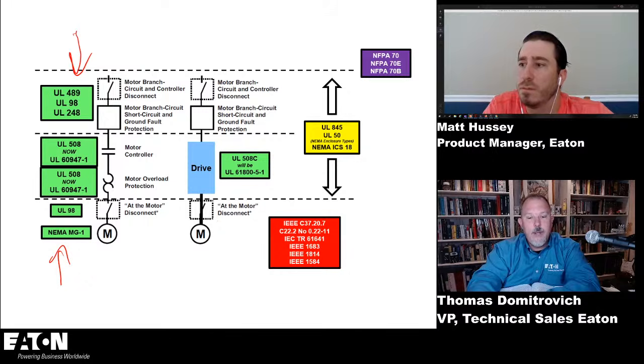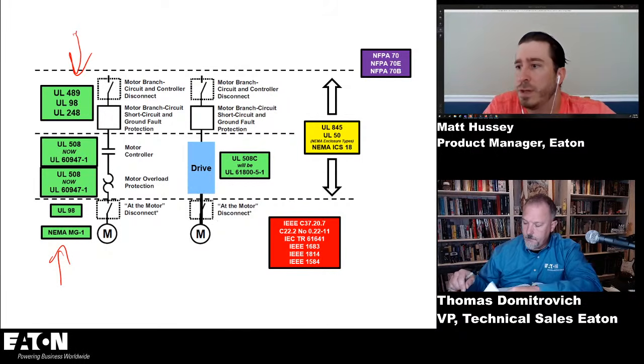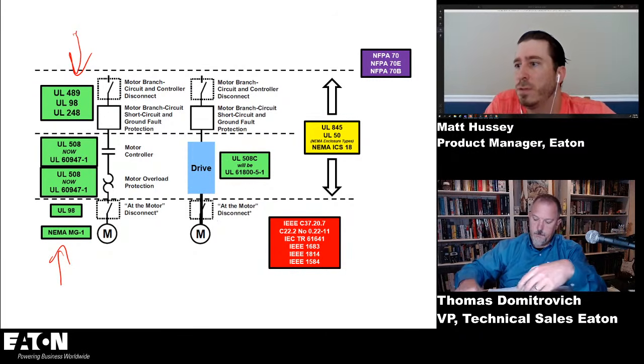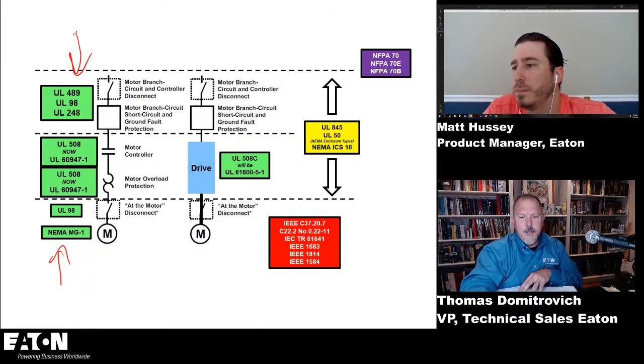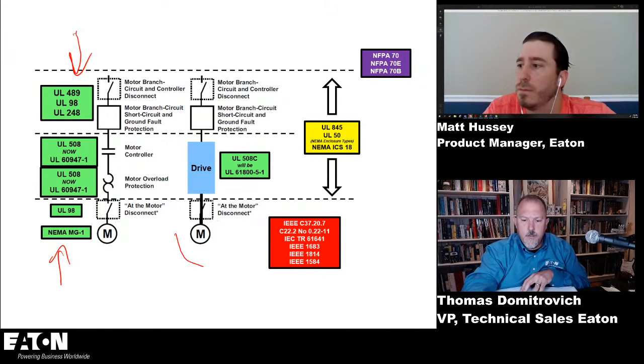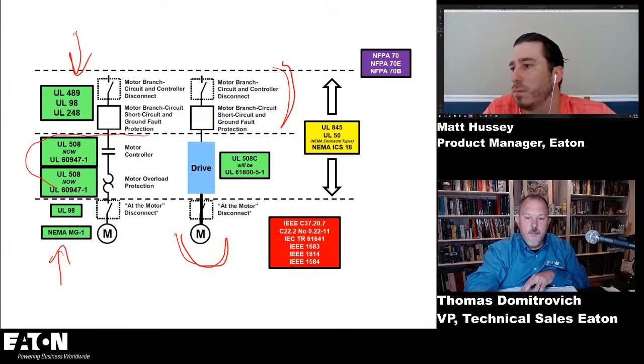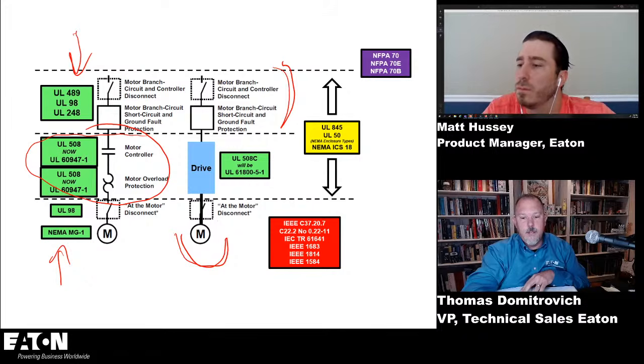And you say UL 508 now, UL 60947. Did a transition happen there? Yeah, there was a harmonization there with UL 508 as well as IEC 60947. Now it's a unified standard to work off of. And then we've got another UL 98 switch down there for the local motor disconnect. And what's this column over here? It includes the drive. That's the big difference there, right? Yep. So you have pretty much everything the same here, but that drive replaces all of that equipment, the motor overload protection and your controller, and it provides that interface between the power distribution system and the motor, and controls that circuit.